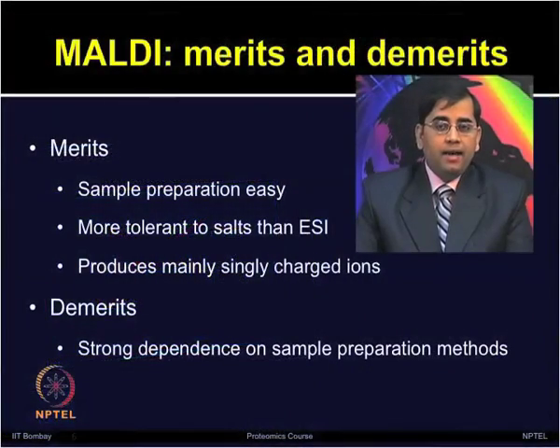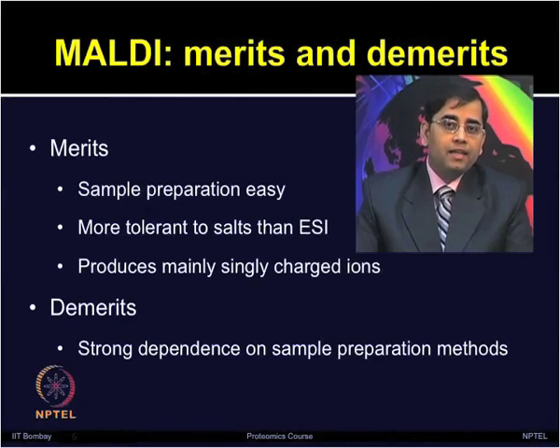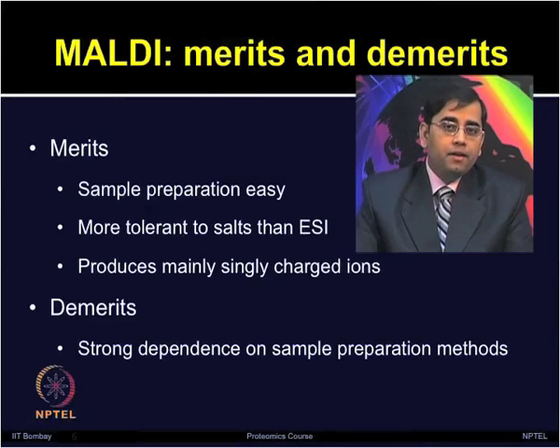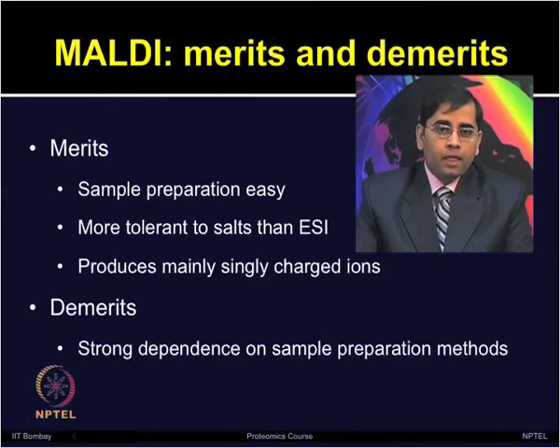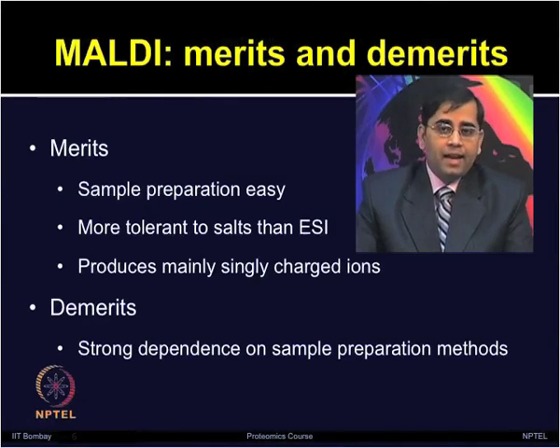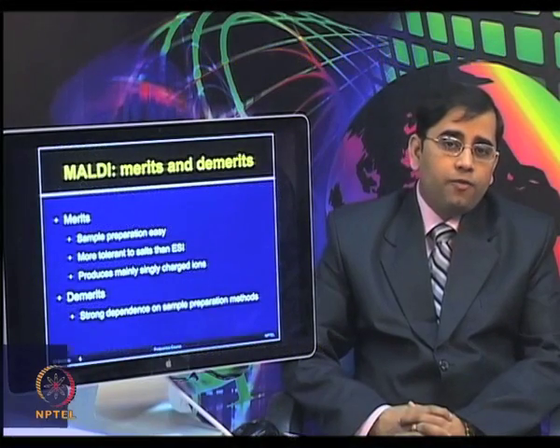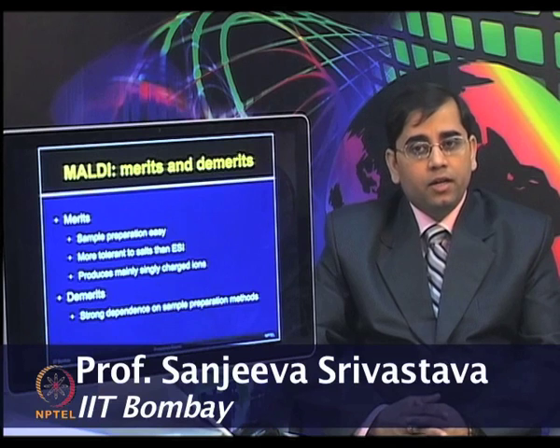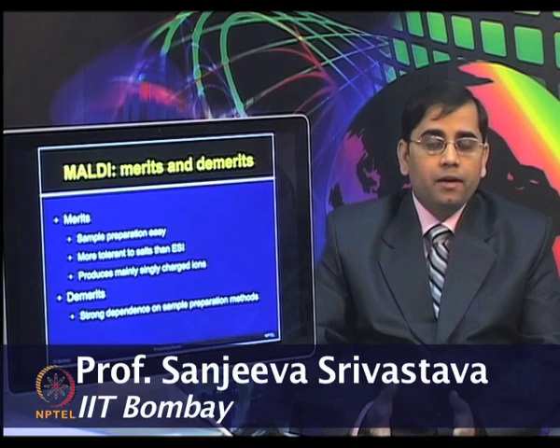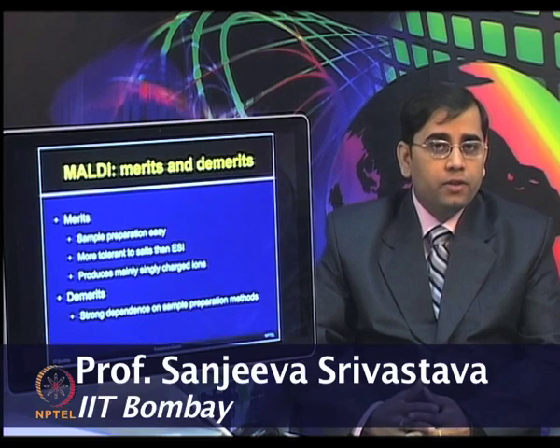The various advantages of using MALDI as an ionization source include very easy sample preparation, and high tolerance to salt as compared to electrospray ionization methods. MALDI produces singly charged species, and most analytes can accept a single proton. This single-charge character can result in some molecules having large mass-to-charge values; therefore, MALDI is typically integrated with TOF mass analyzers, which can provide the m/z range for large ions as well.